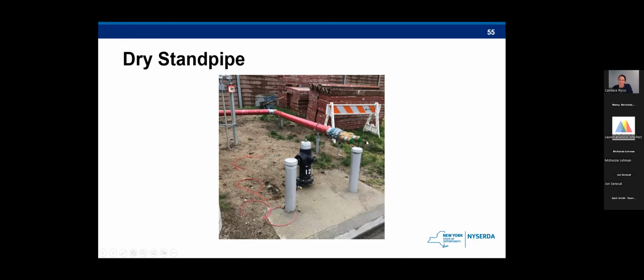And this is from that same project. So I had mentioned very quickly that you could utilize a dry standpipe into these walk-in containers. That can be included as part of the fire suppression system design. So the standpipe is a type of rigid water piping, which is built into the energy storage unit, to which fire hoses can be connected, allowing manual application of water to the fire.